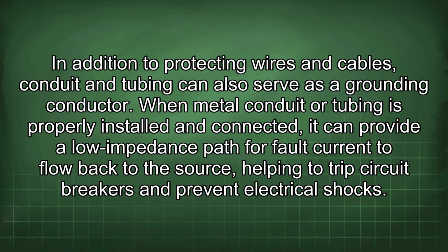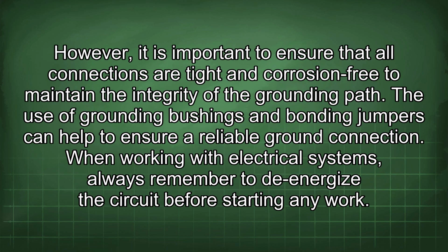In addition to protecting wires and cables, conduit and tubing can also serve as a grounding conductor. When metal conduit or tubing is properly installed and connected, it can provide a low impedance path for fault current to flow back to the source, helping to trip circuit breakers and prevent electrical shocks. However, it is important to ensure that all connections are tight and corrosion-free to maintain the integrity of the grounding path. The use of grounding bushings and bonding jumpers can help to ensure a reliable ground connection.